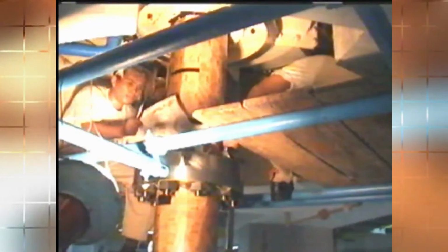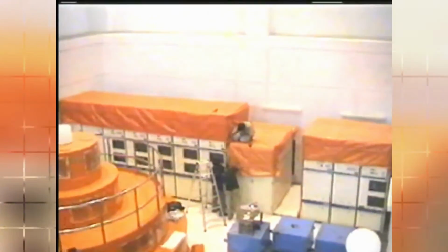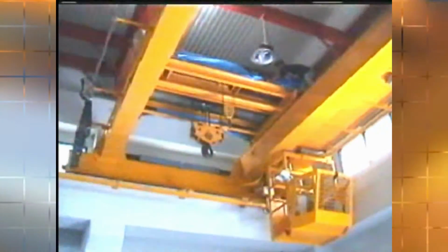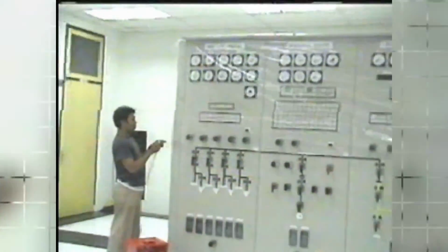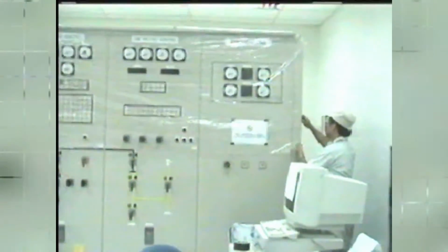After installation works were completed, commissioning tests could not be performed because the penstock is not yet installed and the impounding has not yet proceeded. For 1.5 years, long-term storage is performed as a countermeasure for the power plant. In this period, every 3 months our designers perform inspection and countermeasures for all items of the equipment, especially for turbine and generating equipment, and temporarily energize the 20 kilovolt distribution line from Tulungagung substation up to the terminal pole in Wonorejo power station for prevention of theft during long-term storage.